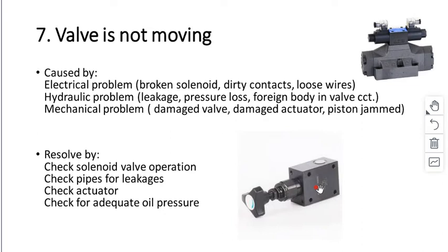Bear in mind that solenoids gobble up a lot of current. And even though you may have all the voltages, if the contacts are not squeaky clean, it may not be capable of pushing the current through. It just behaves like a resistor. And if that is the case, you don't get your 3-4 amps or whatever the solenoid needs to operate. And then the valve won't work.